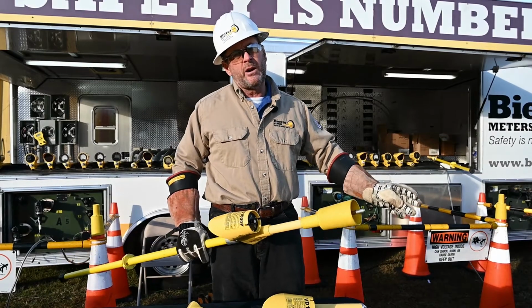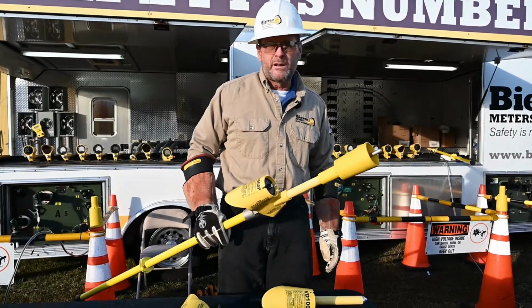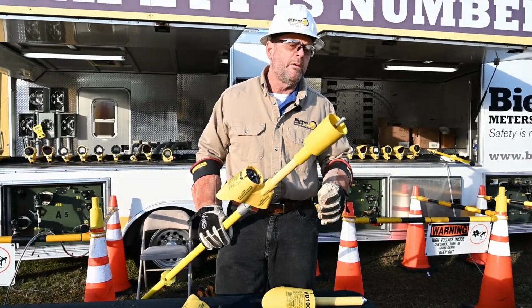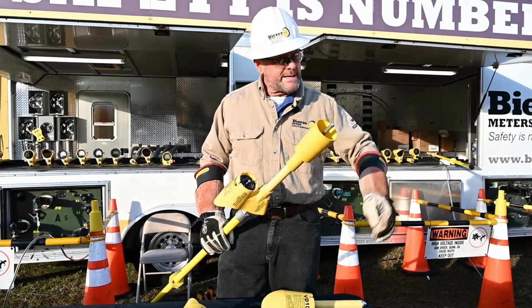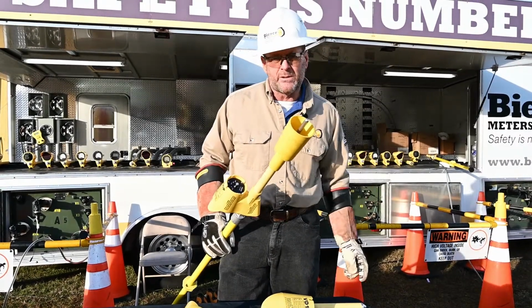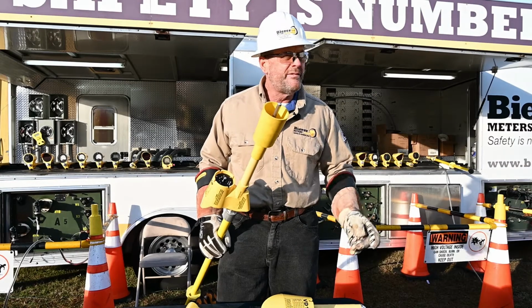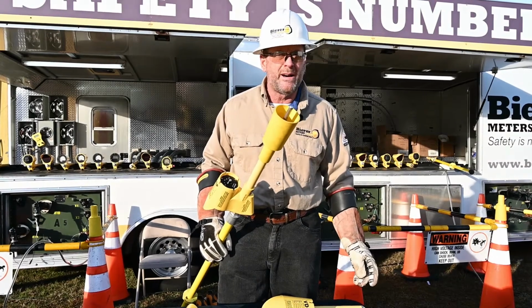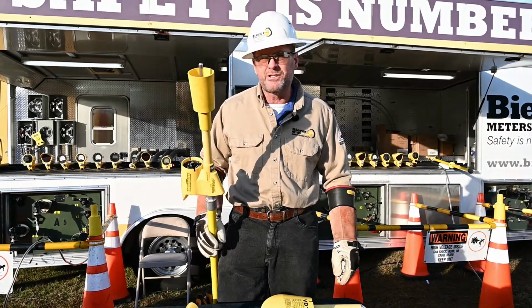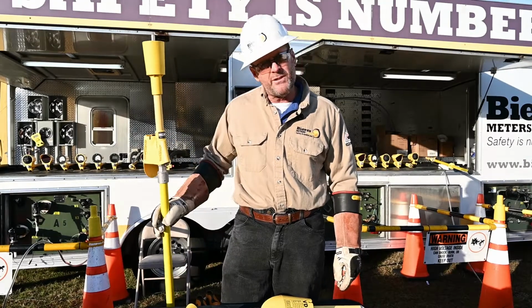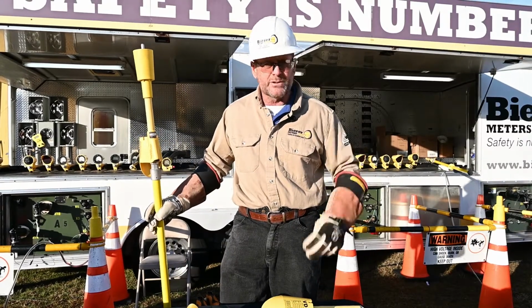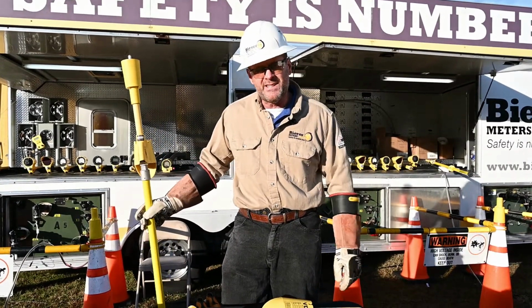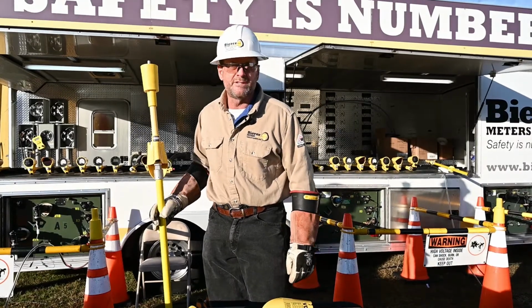Guys are getting hurt on induction all around the country. So we don't want the lineman to make contact with the TPG on the conductor without verifying a lack of induction as well. This should actually be changed, I believe, in the OSHA regs. They should be looking for a lack of all three. For some reason it hasn't been changed yet.